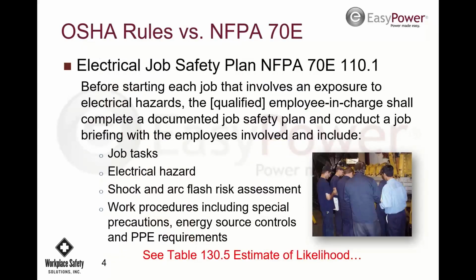NFPA 70E says we have to do a job safety plan, and with that plan we have to do a job briefing, which requires us to assess hazards. There's an expansion of that in NFPA to not just assess hazards but also the risk levels associated with those hazards. We'll talk about that a little bit. The big thing with the safety plan and assessing the hazards gets into the tables and the labels from an arc flash standpoint. Shock is what it is. We have to know what to do for rubber gloves and all those kinds of things. But for arc flash, it's a little more vague, especially if an arc flash analysis has not been done.